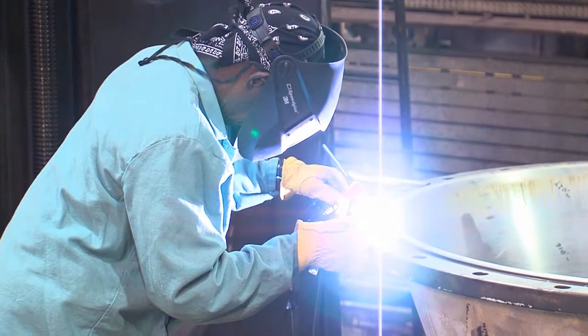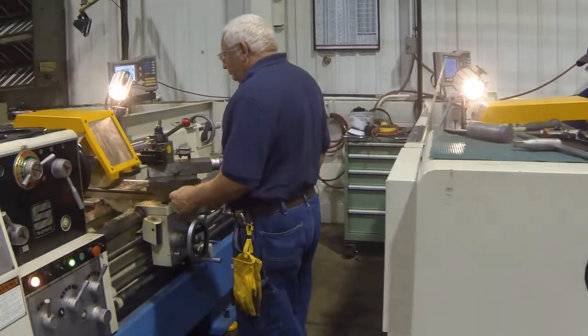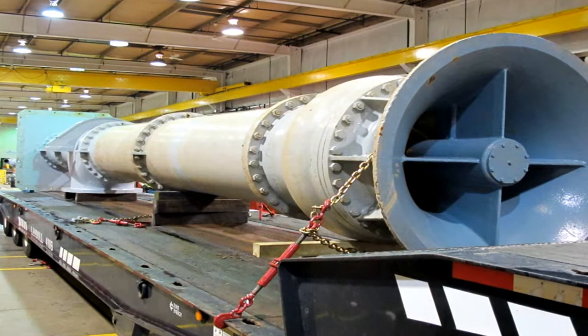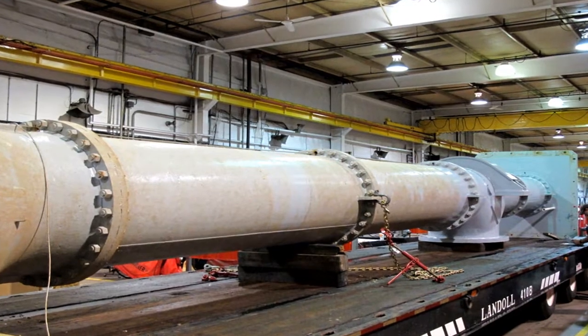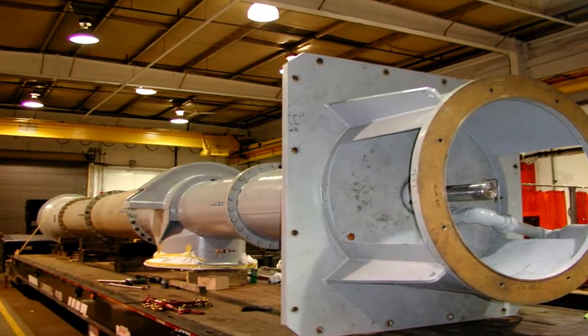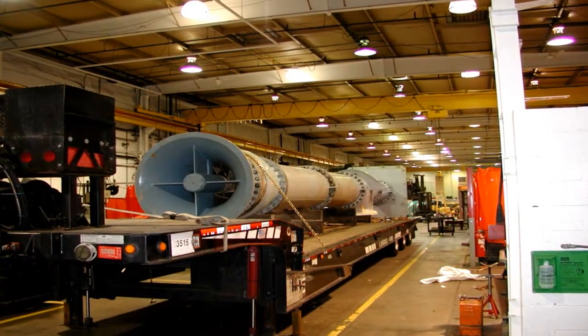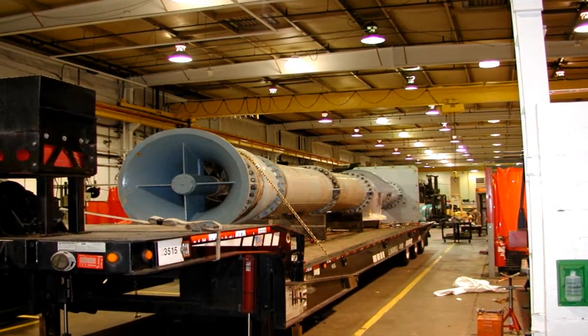The Lark Maintenance Center is part of the Duke Energy team, so there are no competing priorities. Serving the Duke Energy generating fleet is their only mission. We had an RL pump at Catawba that failed during startup after a vendor rebuild. The pump basically seized up during startup. They'd done some initial inspection and some on-site repairs. At that point, the decision was made to pull it out and send it here for a total disassembly and inspection to determine what went wrong. We worked two shifts, 12 hours a day, and completed this project in eight days. This is a testament of our commitment to the nuclear fleet, and also to the coal-fired, gas-fired, and hydro units as well.